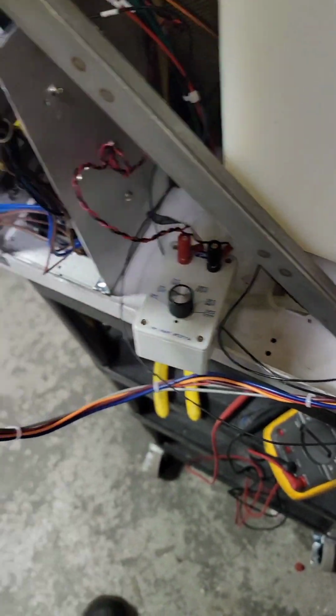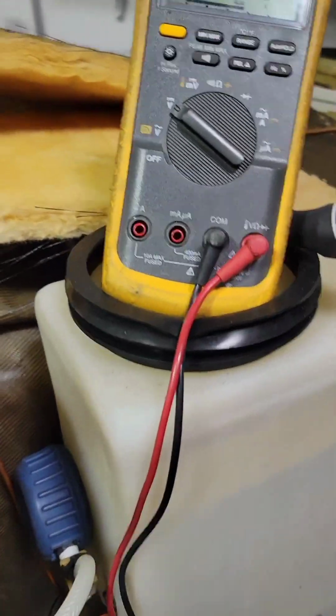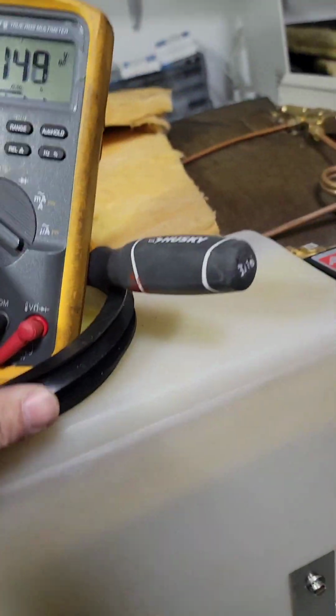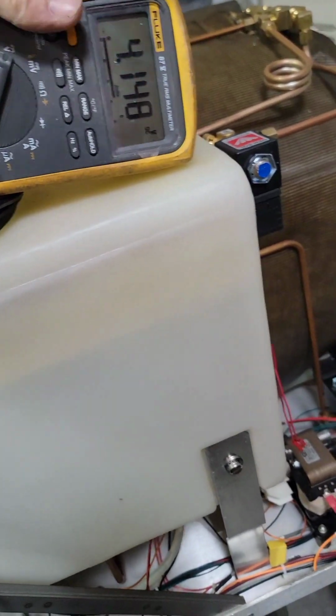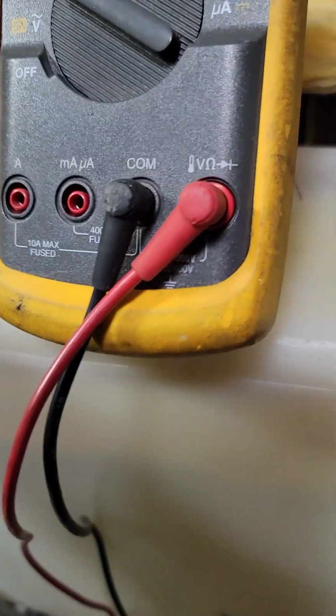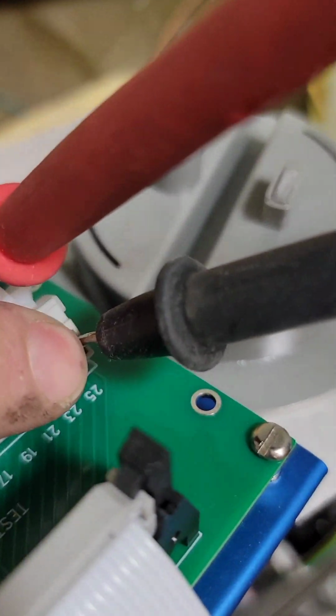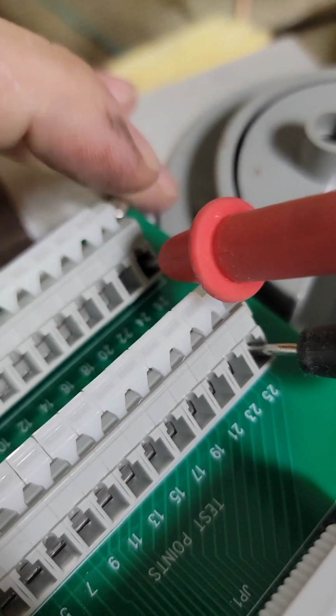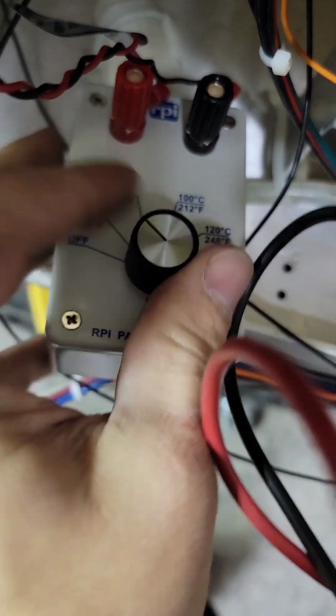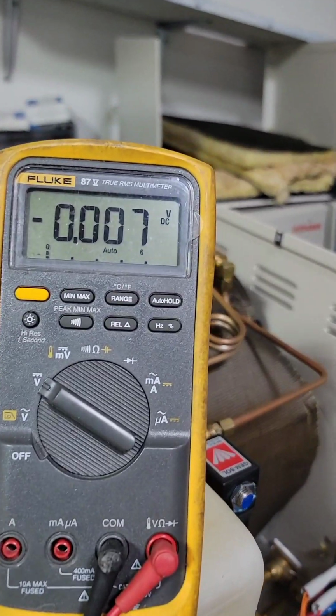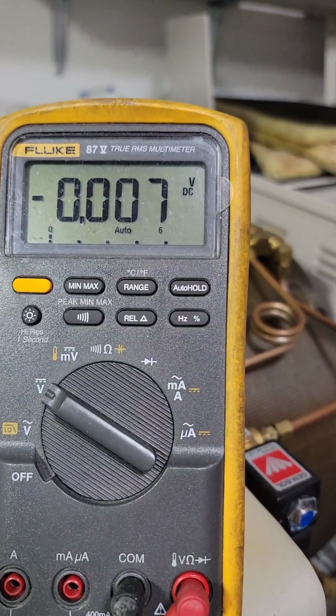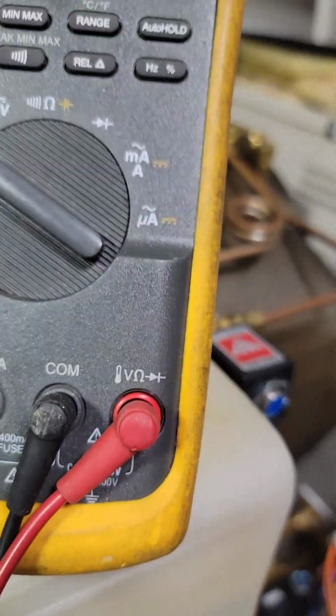Okay? So the first calibration we're going to do is temperature calibration. Set your meter to voltage DC, direct current. Everything we do in the calibration is VDC. So, I should put this somewhere that's going to be stable, where you can see it as you're calibrating, and it isn't going to fall down. It isn't going to be a pain in the butt to see. There we go. So, now we put your negative probe on test point 25, positive probe at test point 26. Put it on your PT100, set that to 32 Fahrenheit, 0 Celsius. And we should be seeing negative 0.005. So it's supposed to be 5.1 millivolts.